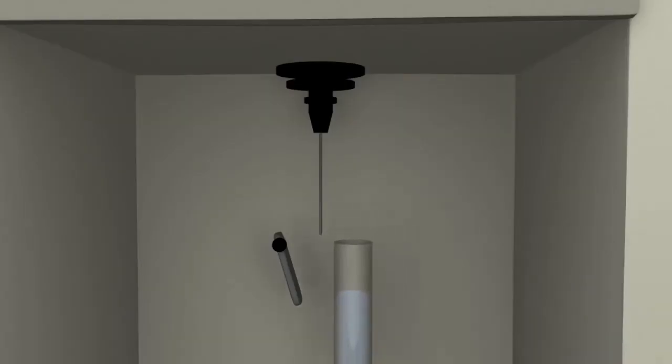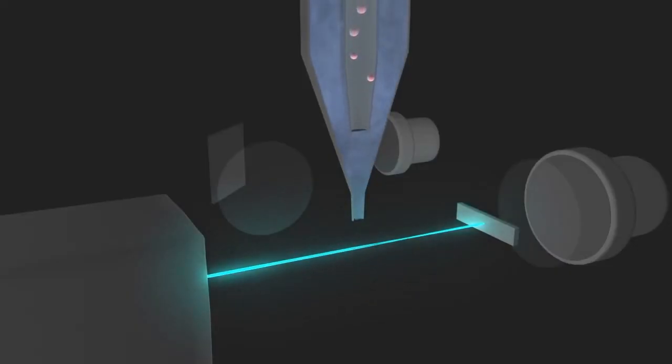Once a sample has been placed in the flow cytometer, the machine will suck up the sample, mix the sample into a stream of saline solution in the cytometer, and lead the cell suspension through a narrowing channel causing the cells to form a single file line before the cells pass through the laser at the interrogation point.